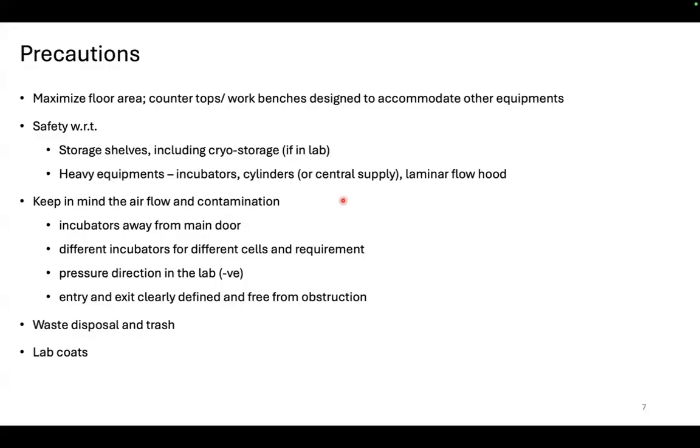Generally, it's around 5% CO2 that's given in these incubators. So you have incubators connected to a carbon dioxide supply. Now, that supply can be in-house if you are the only lab that's doing cell culture. So you'll have one or two CO2 cylinders, and there's going to be a pipe traveling from the cylinder to your incubator. These incubators, which are at 37 degrees, have the option to control that. This is 5% CO2. It'll keep it between 5, 5.1, 4.9, like that.